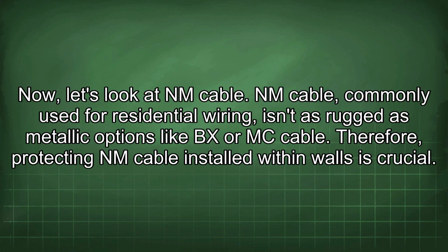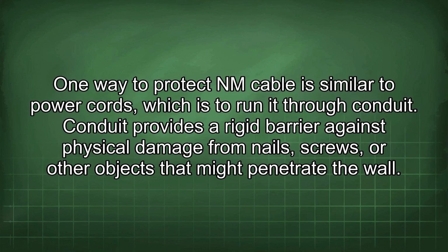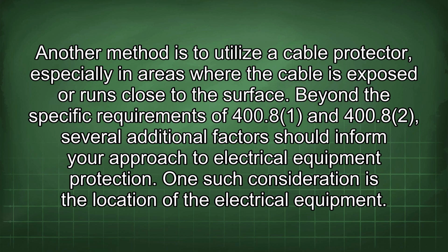Now let's look at an NM cable. NM cable, commonly used for residential wiring, isn't as rugged as metallic options like BX or MC cable. Therefore, protecting an NM cable installed within walls is crucial. One way to protect an NM cable is similar to power cords, which is to run it through conduit. Conduit provides a rigid barrier against physical damage from nails, screws, or other objects that might penetrate the wall.